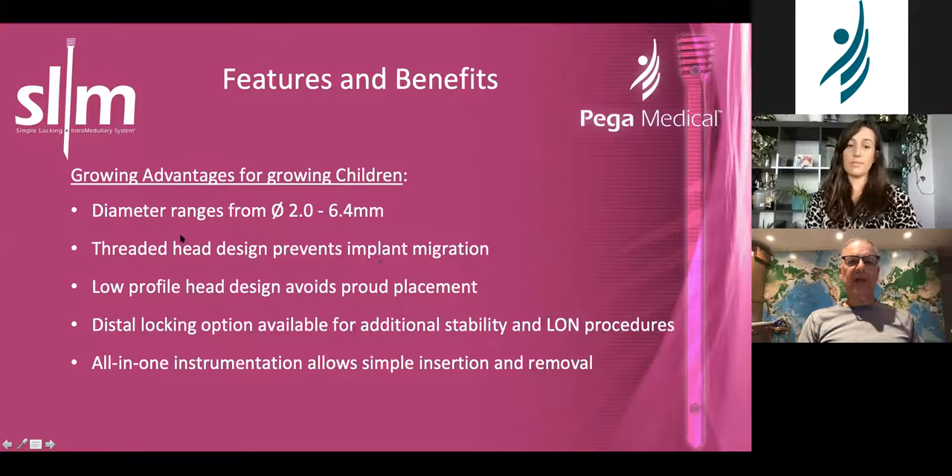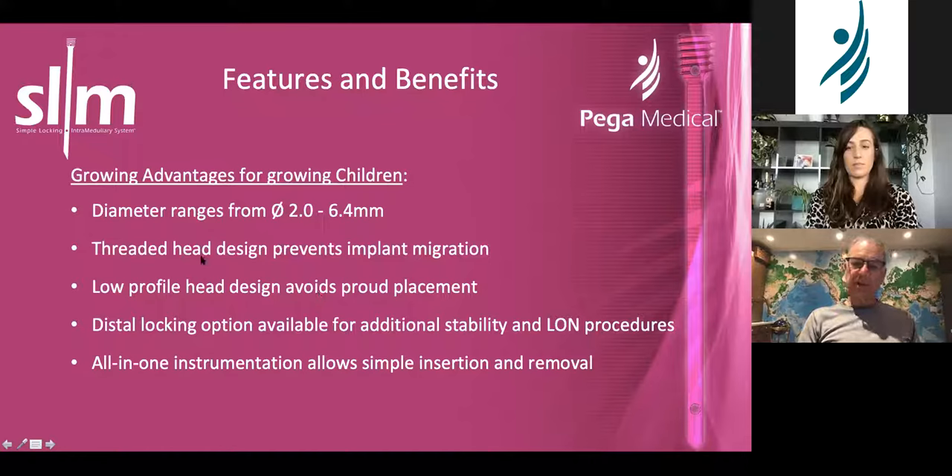The threaded head design — what the nail looks like — is a little different from the Fassier-Duval in that these are sharper threads and it is conical. The reason it's conical: even if you can't screw it into bone, if you bang on it, it'll actually impact itself into the bone — it works very nicely that way. It's a low-profile head that avoids proud placement, and because the ends are sharp, these are not blunt threads like the Fassier-Duval — these are sharper threads. We'll talk about locking in a bit, and it's got its own instrumentation which is rather nice.